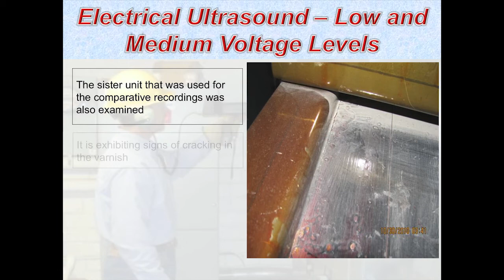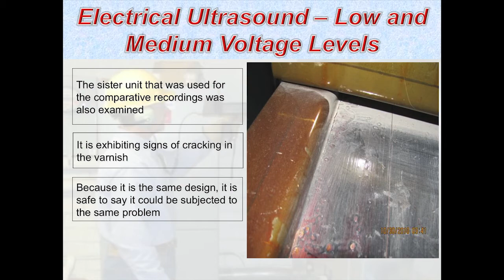Eventually it's going to have the same delamination in the middle, thermal effects, and I believe ultrasound, because we didn't have any at the time of recording. So a whole year goes by with this bickering back and forth between the customer, Square D, and the contractor - just stalling for time. Going back one year later, that core temperature is still increasing, still coming from inside. When you go back for another service, what do you think you want to do if you had something the previous year? Let's compare it again.